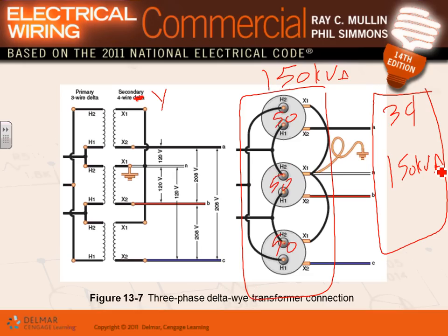What do you say about it? Well, from that point of view, because typically these are owned by utilities, this type of arrangement is actually a service. So if they have a short and one burns, how would they go through it? How would they do that? Oh, we rehook them? Very easy. Here's one transformer, here's another transformer. You hook them up as open delta. One of them is gone now. From this side the same way, an open delta, and this will be grounded.